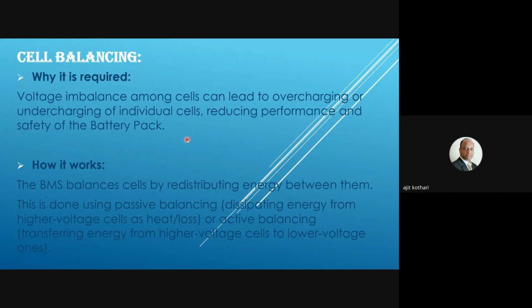So all these are the drawbacks of cell imbalancing. During charging it will have an effect, and during discharging it will give bad performance. To increase performance, all cells should be at the same level. Then only your battery pack will give you 100% of the expected capacity, or the performance of that battery pack. Now, how does it work?